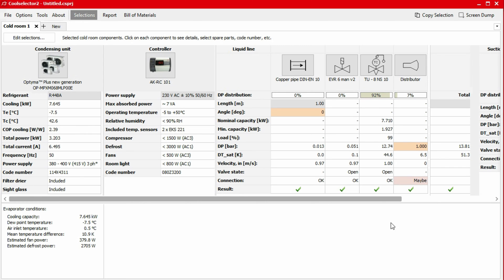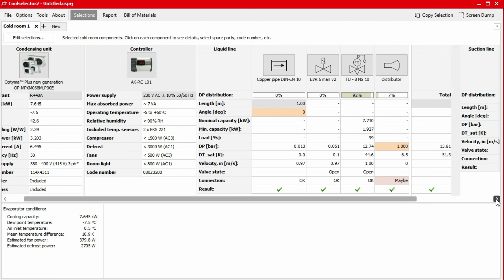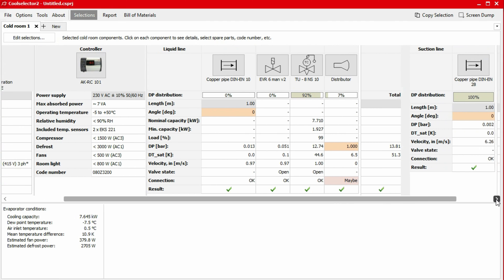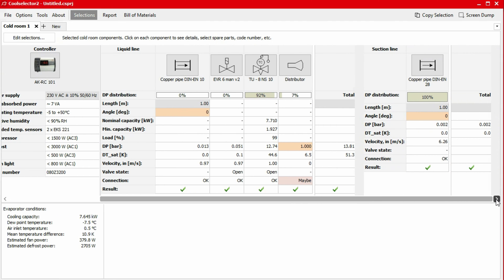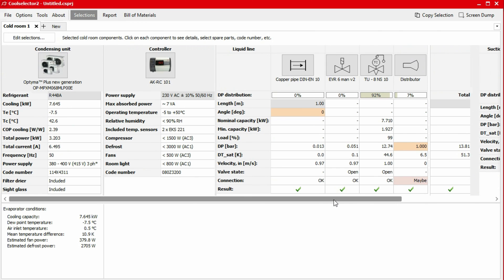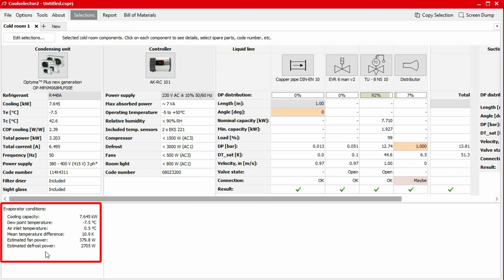The application will now display all the suggested components for the cold room. The condensing unit is selected based on your required cooling capacity. All other components will be sized and selected based on the condensing unit found, as well as the requirements for the cold room. Danfoss doesn't provide any evaporators. However, the application does calculate all the required values which can be provided to an external supplier for selection of the evaporator.